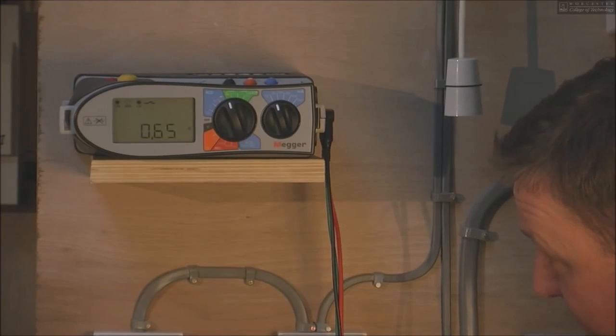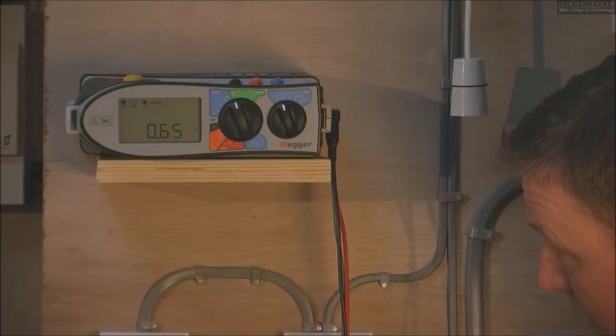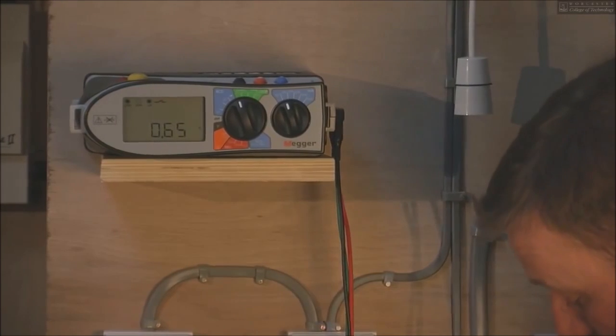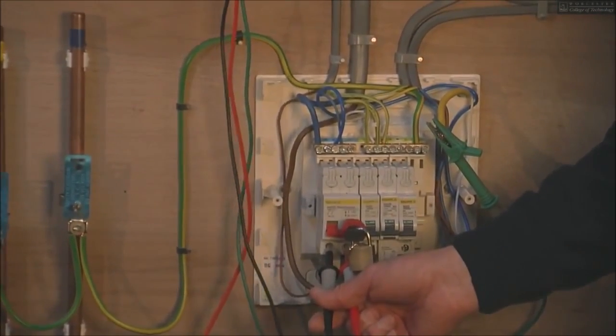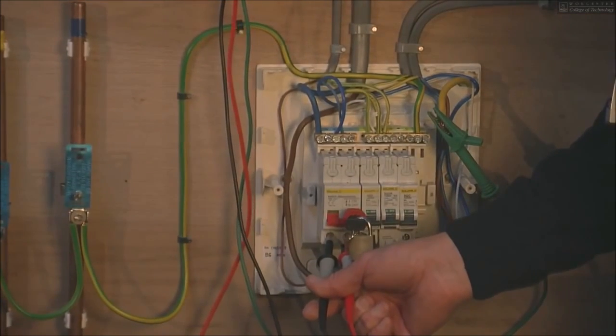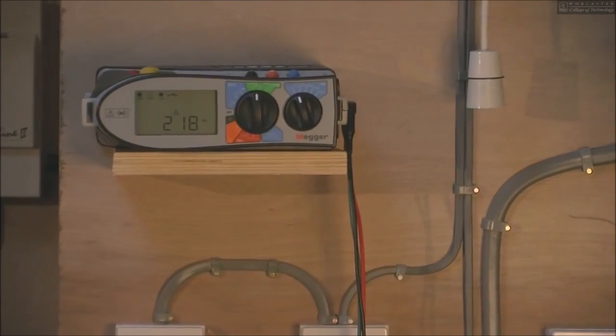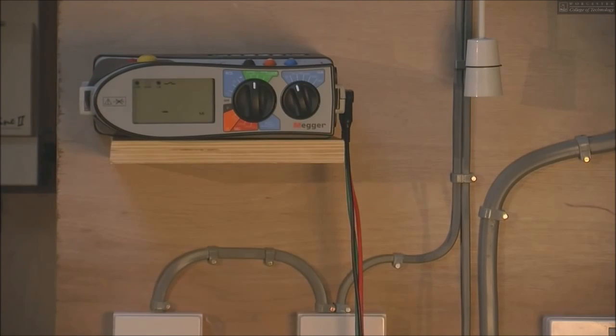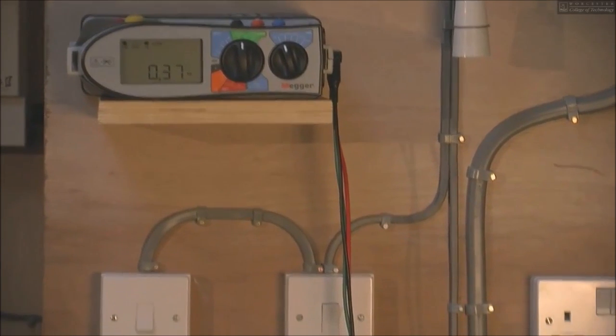It does take a bit of time, and we have 0.65 ohms. This value is then compared against the relevant regulations. We can then go on to do the prospective fault current test. Simply move the dial across, and this will give us a value in kiloamps. This is vitally important, because if the current is greater than the rating of any protective devices installed in the system, they could potentially explode. As you can see, we have 0.37 kA. These are rated at 6 kA, so they are safe.